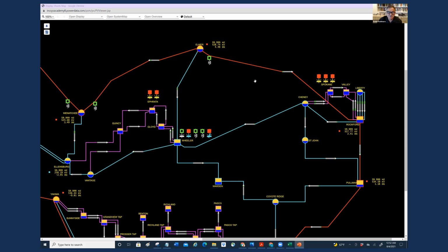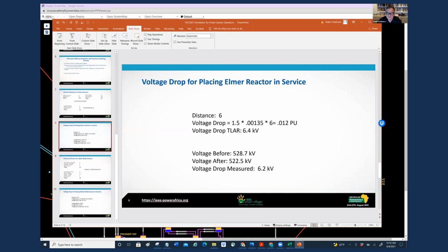All right, so let's take those calculations and see what happens when we compare the TLAR estimates with the actual operations from switching on the power simulator. If we take Elmer, we're starting out at 528.7 kV, and we put the reactor in service, and we end up with 522.5. Let's just summarize the calculation. We start with 528.7, we end up with 522.5. We measure a drop of 6.2 kV. From the TLAR calculation, we got an electrical distance of 6, which was predicting 6.4 kV. Given the complexity of the system that you've seen, that is a very good TLAR estimate.